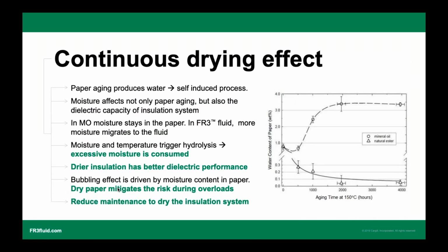So what does this hydrolysis, or continuous drying effect, mean? It means that this fluid loves moisture. When there is free moisture, it eats it, as simple as that, and when it eats, it has to generate some byproduct. The byproducts are nothing but fatty acids. Those acids are not corrosive or aggressive like those in mineral oil. They are non-corrosive, less active acids, the same acids humans eat, like the omega-3 and omega-6 acids we eat a lot of. It's nothing but digestive acids. There are studies also attached in the standard, in the annex of 60076 part 14, that these acids interact with the cellulose and enhance its electrical and mechanical properties.